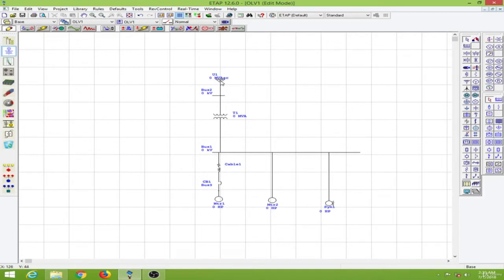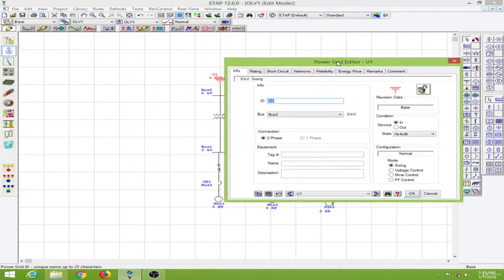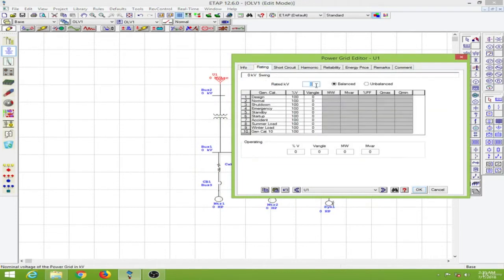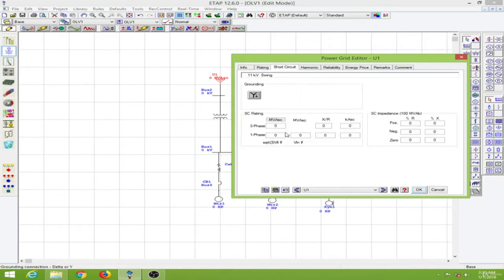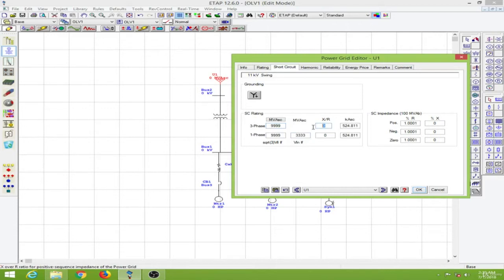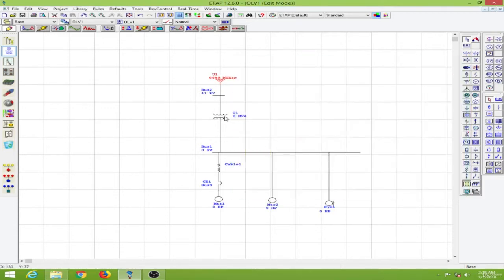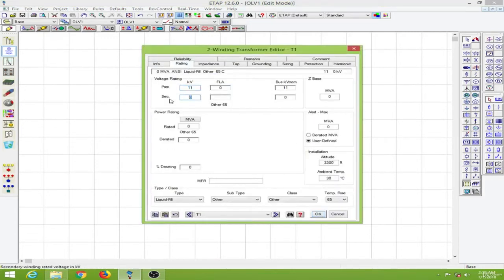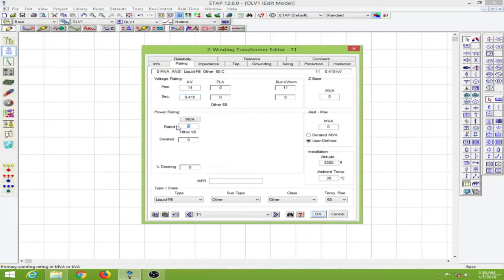Now going to the ratings for every element. I will write the power grid for 11 kV and the short circuit values will be infinite as possible. So that's done. Now for the transformer I will use 11 kV to 415 volts 5 MVA transformer.